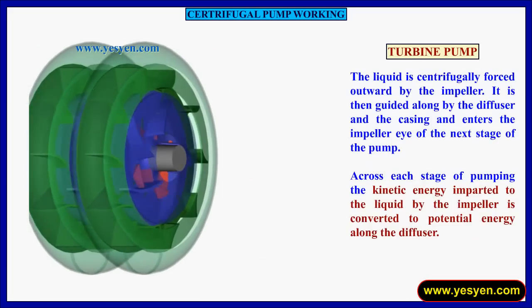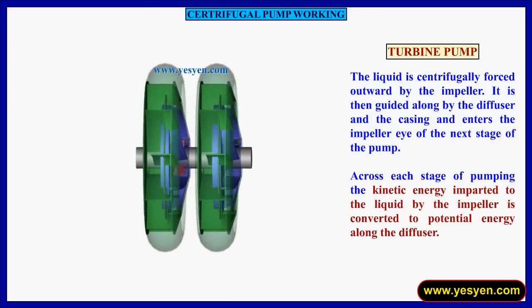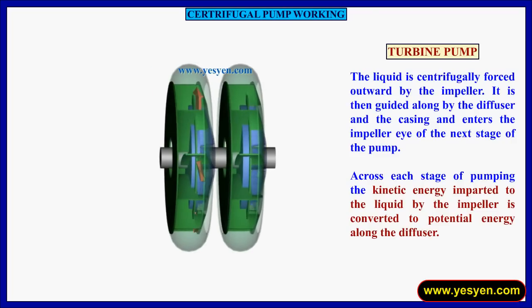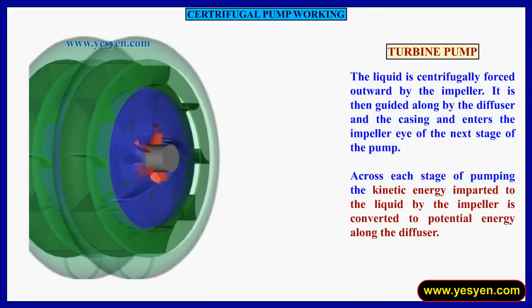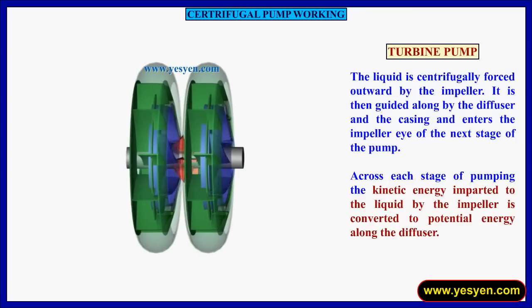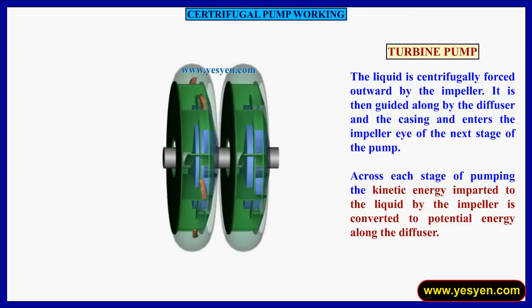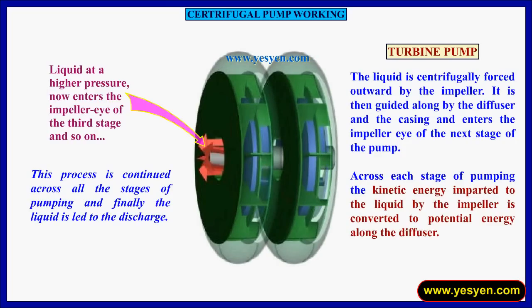The liquid is centrifugally forced outward by the impeller. It is then guided along by the diffuser and the casing and enters the impeller eye of the next stage of the pump. Across each stage of pumping, the kinetic energy imparted to the liquid by the impeller is converted to potential energy along the diffuser. Liquid at a higher pressure then enters the impeller eye of the third stage, and so on. This process is continued across all the stages of pumping and finally the liquid is led to the discharge.